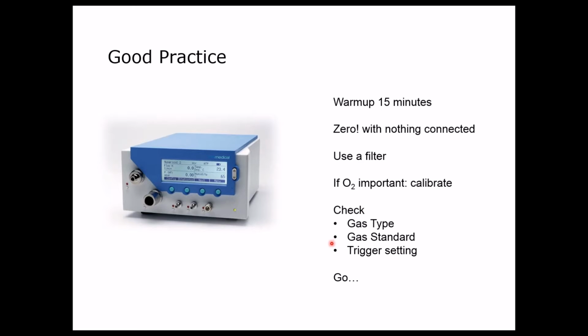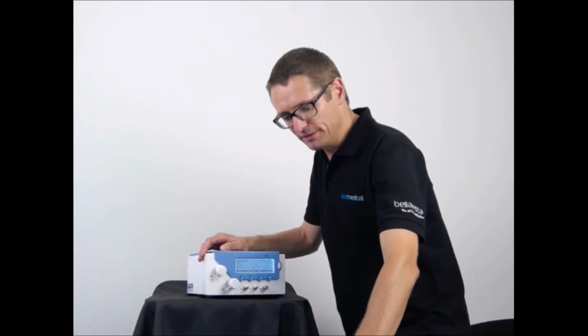Before we actually start working, we have to make sure that the gas type is set up correctly. We have to make sure the gas standard is set the same as my ventilator, and we want to make sure our trigger settings are working. Particularly the trigger settings can also be changed later on if we realize that anything is funny or strange or not matching up with the ventilator. So let's start with the practice. I will zoom now on the device itself.